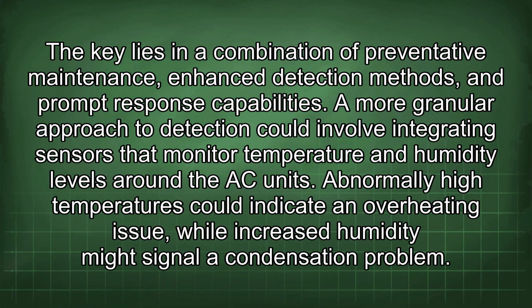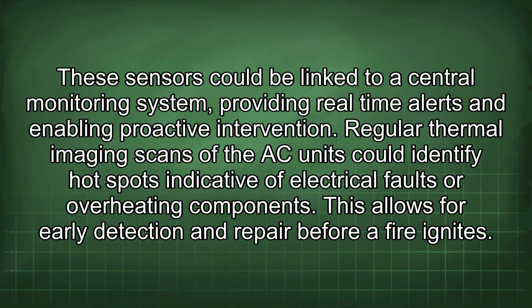A more granular approach to detection could involve integrating sensors that monitor temperature and humidity levels around the AC units. Abnormally high temperatures could indicate an overheating issue, while increased humidity might signal a condensation problem. These sensors could be linked to a central monitoring system, providing real-time alerts and enabling proactive intervention. Regular thermal imaging scans of the AC units could identify hot spots indicative of electrical faults or overheating components. This allows for early detection and repair before fire ignites.